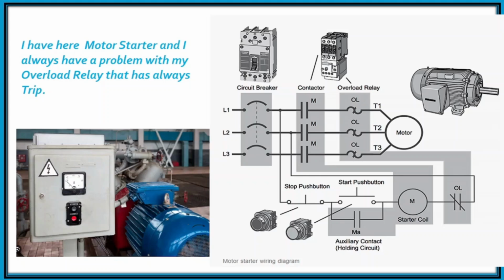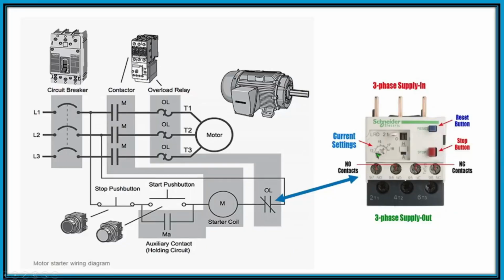I have here a motor starter that I always have a problem with, because my overload relay has always tripped. Do you know how to check an overload relay? This is the overload relay, and to check it using the multimeter, switch to ohms. The 95 and 96 should be closed and the 97 and 98 should be open.